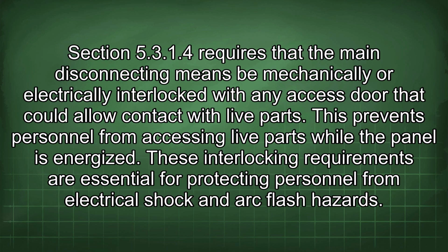Section 5.3.1.4 requires that the main disconnecting means be mechanically or electrically interlocked with any access door that could allow contact with live parts. This prevents personnel from accessing live parts while the panel is energized. These interlocking requirements are essential for protecting personnel from electrical shock and arc flash hazards.